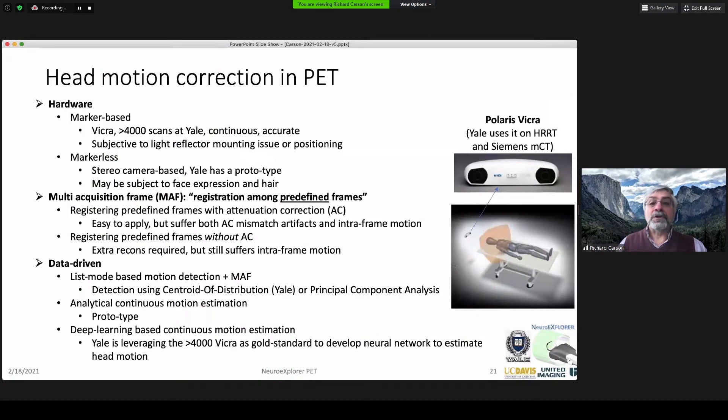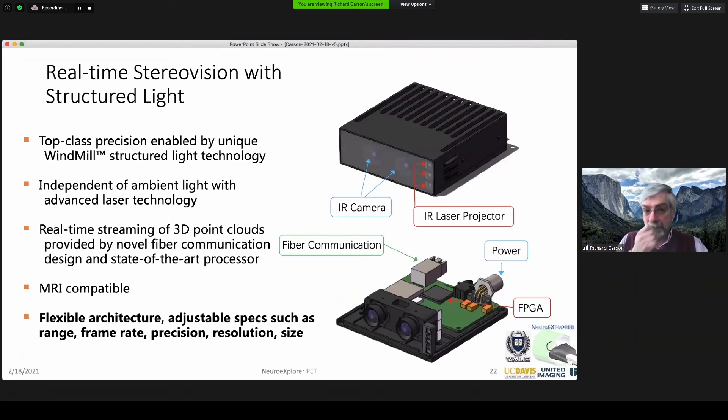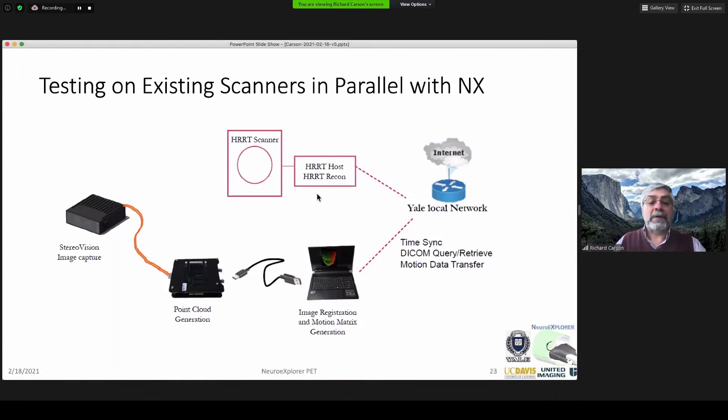Head motion is critical and has been a huge topic of conversation in PET for a long time. We've been using the VICRA for tracking head motion, which requires mounting a tool on top of the patient's head — it works well, but is still limiting. The approach we're going to use is stereo cameras with structured light, which we think is the smartest way to produce a reliable measure independent of count level. This is an off-the-shelf machine we've already begun testing, and it's already MR-compatible. Since we're already using this on our HRRT with the VICRA, we can do a head-to-head comparison — that work is already beginning at Yale, so we'll get ahead of the curve before the NX is completed.